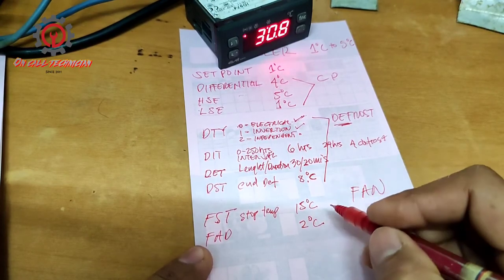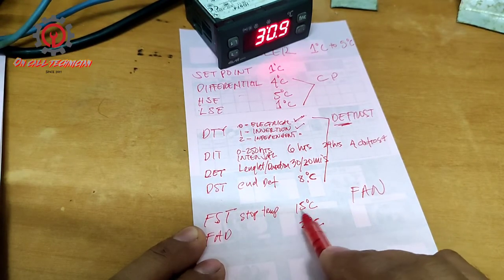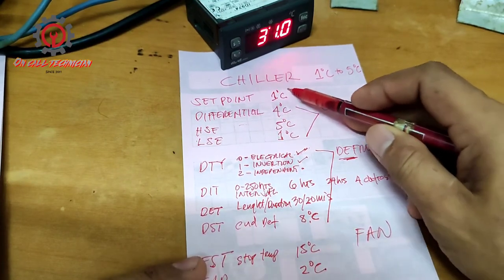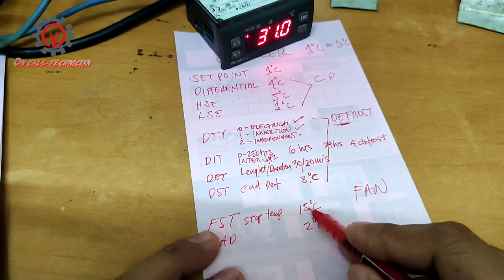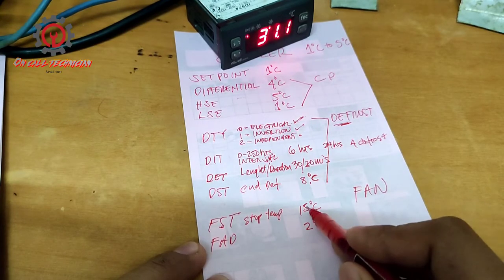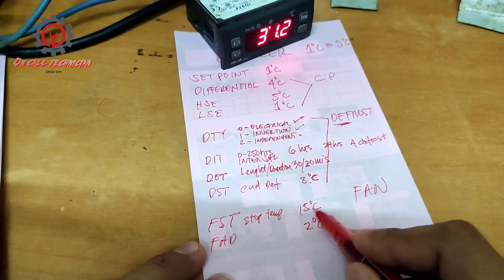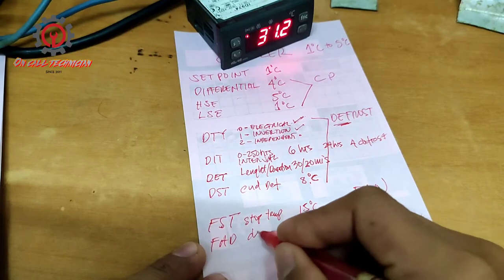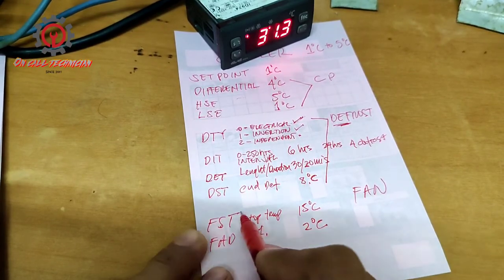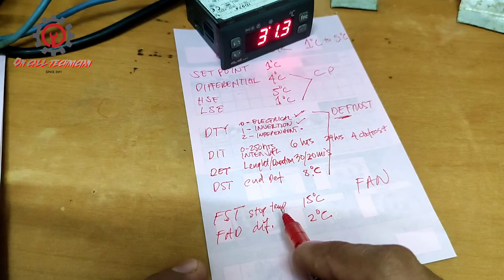The fan folder also has a differential, FAD. I'm going to put two degrees Celsius here. This means the fan stops when it reaches 15 degrees Celsius, and once the compressor starts pumping again and the temperature drops to 13 degrees Celsius — because 15 minus 2 is 13 — the differential is satisfied and the fan motor will run again. That is the purpose of the fan differential.